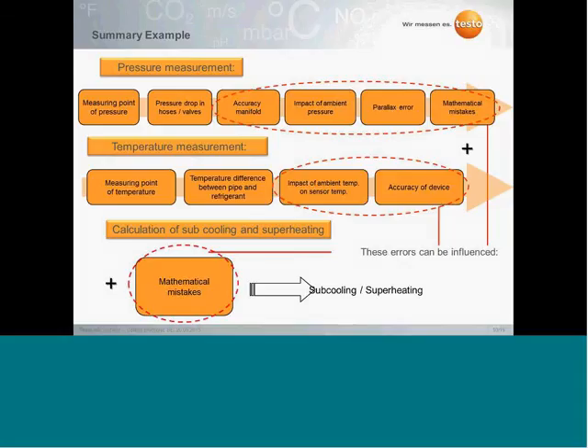On this slide, which of these factors can be influenced by us? That means which of the factors can reduce the risk of failure or avoid the failure at all. By using, for example, digital manifolds, especially the ones you see marked red here can be avoided. So we can get better accuracy from the manifold.